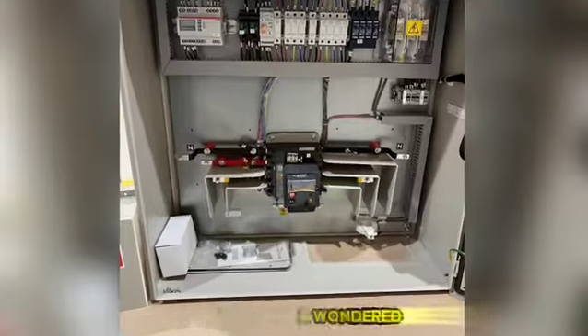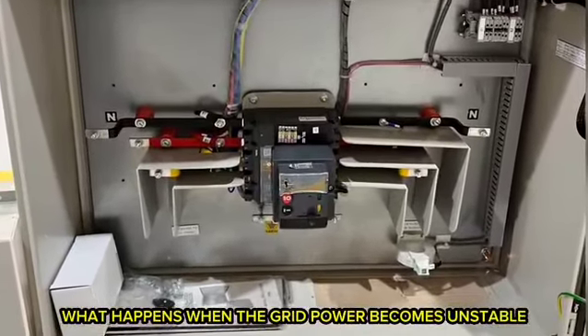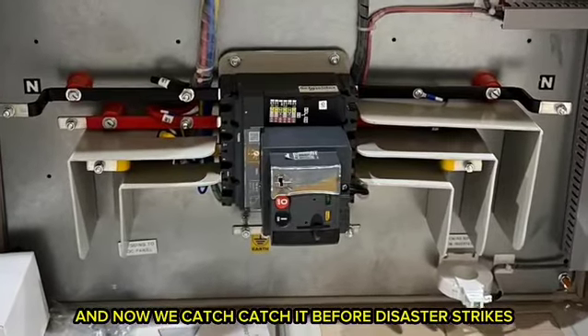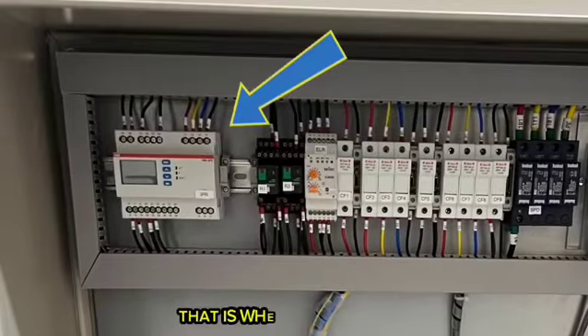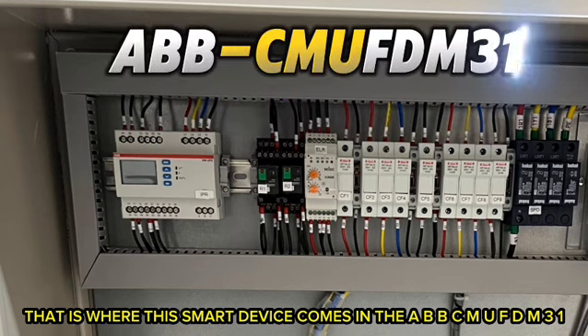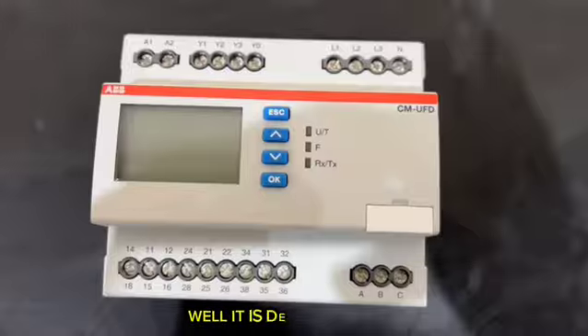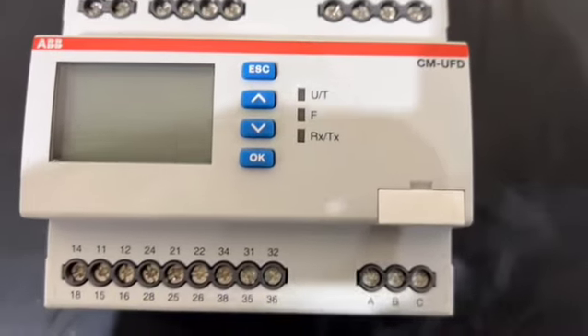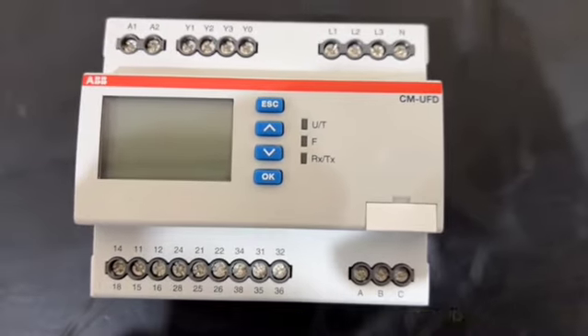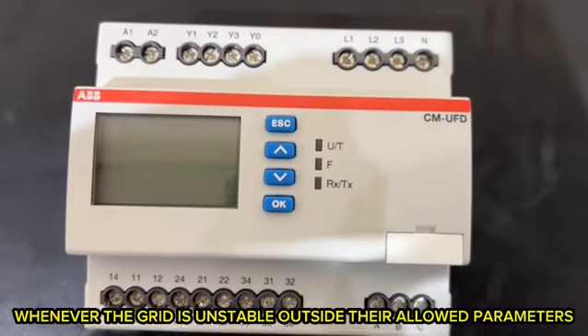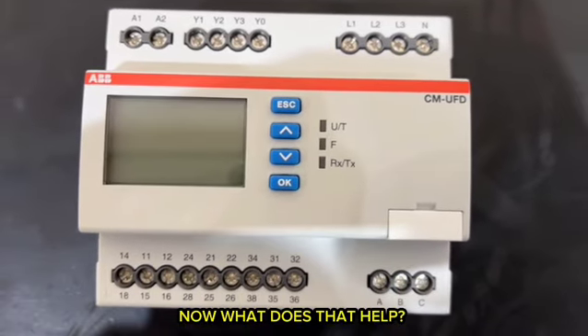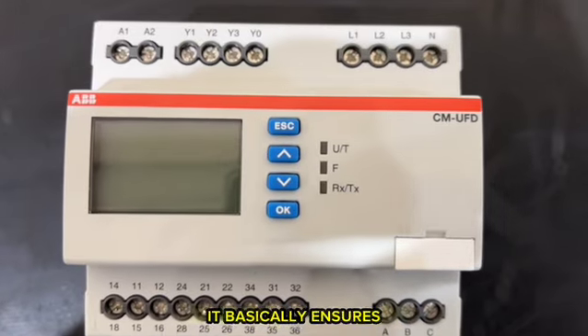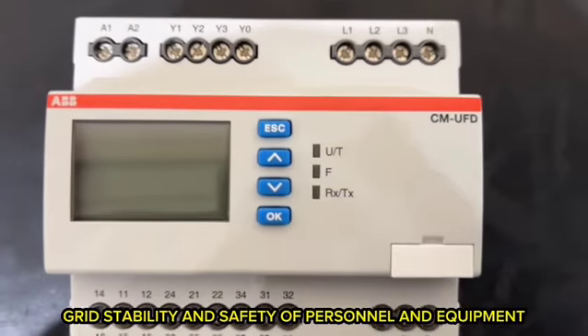Have you ever wondered what happens when the grid power becomes unstable and how we catch it before disaster strikes? That is where this smart device comes in, the ABB CM-UFD.M31. So you may ask, what is the primary function of this device? Well, it is designed to disconnect generators or inverters from the grid whenever the grid is unstable outside the allowed parameters. Now what does that help? It basically ensures grid stability and safety of personnel and equipment.